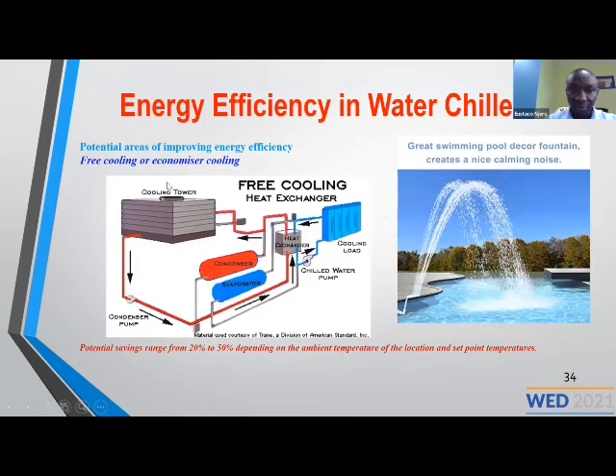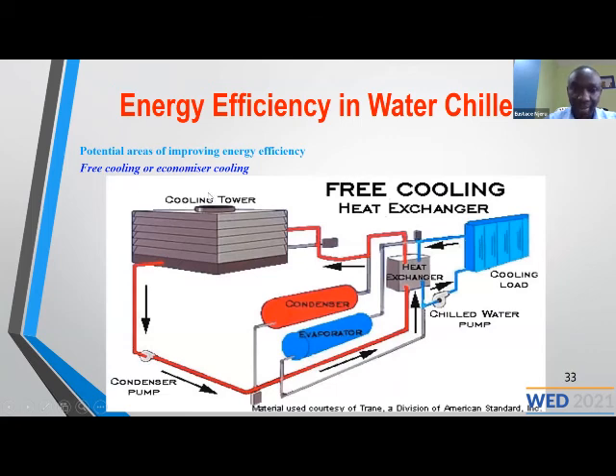But now, if you discover that the external conditions are favorable, they are cold, and the water from the cooling tower can sufficiently cool, instead of using the refrigerant to cool the water for cooling, you can bypass. You can prevent this water from going to the condenser and take it directly to a heat exchanger, then back to the cooling tower. This water will cool the water in the cooling load and avoid going to the evaporator. In that case, you are going to switch off the compressor completely.